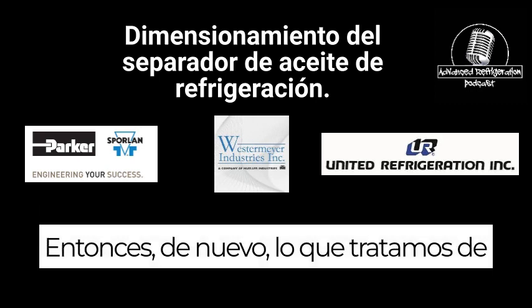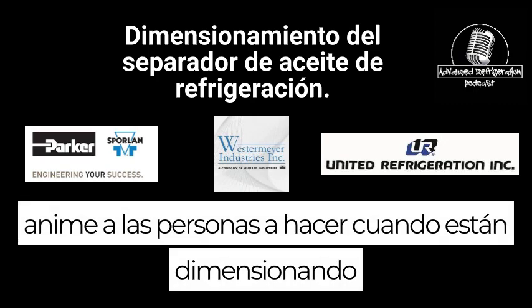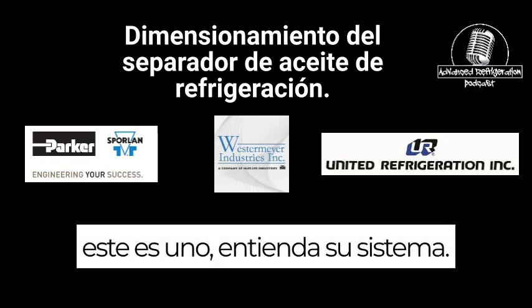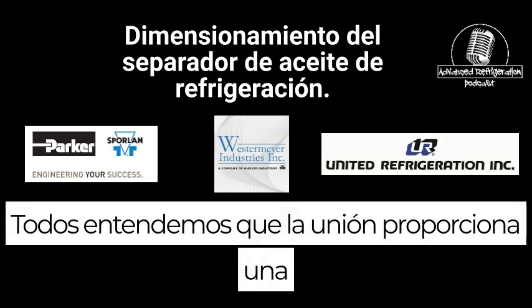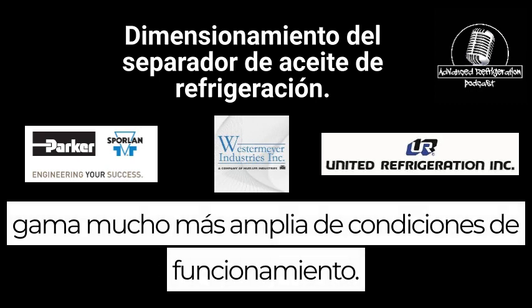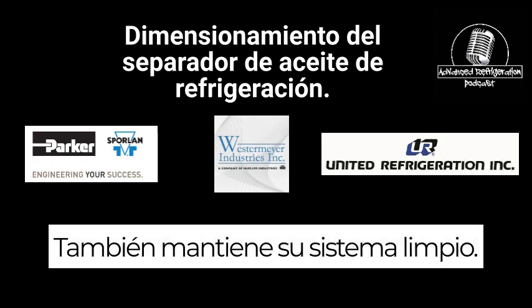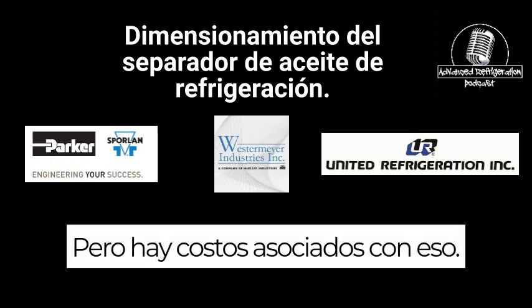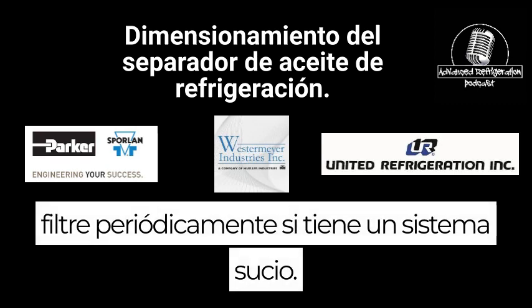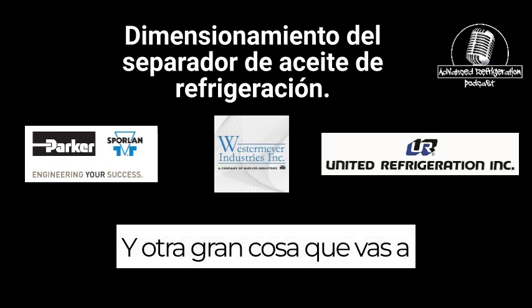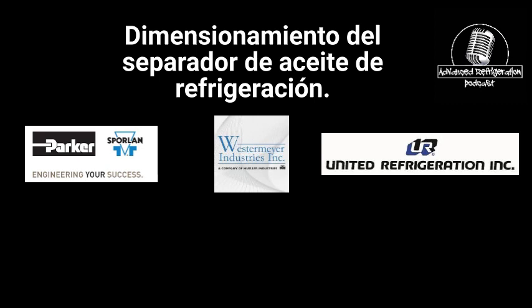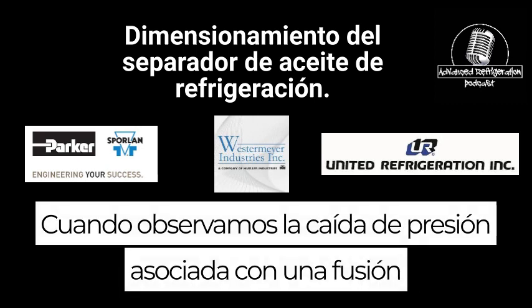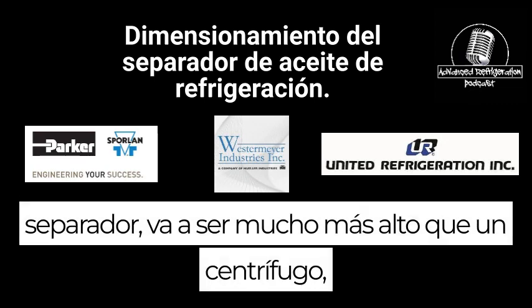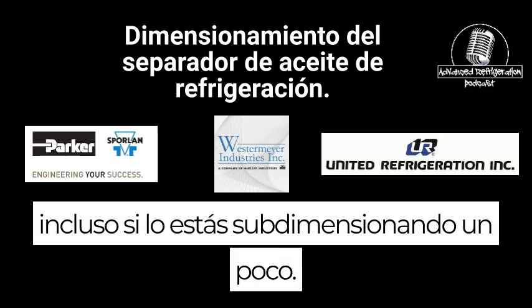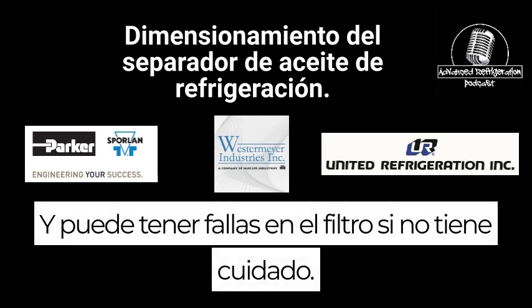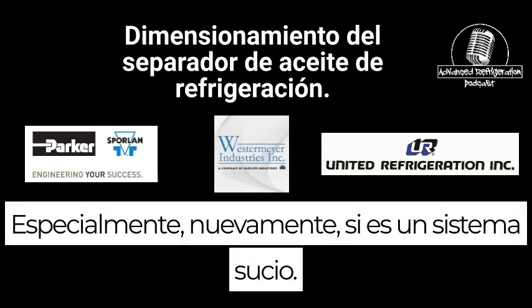Again, what we try to encourage people to do when they're sizing these is, one, understand your system. We all understand that coalescing provides a much wider range of operating conditions. It also keeps your system clean, but there are costs associated with that. You have to go in and change the filter periodically if you have a dirty system. Another big thing you're going to have to monitor is your pressure drop. Pressure drop associated with a coalescing separator is going to be much higher than a centrifugal, even if you are undersizing it a bit. And you can have filter failures if you're not careful, especially if it's a dirty system.